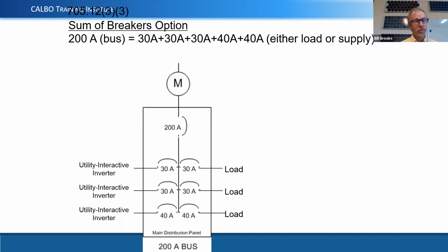And it allows us to put in much more PV, up to, certainly if we're using a 200 amp breaker out of this panel, we could go all the way up to 200 amps, which is 38 kilowatts. That's pretty big on a 200 amp service, more than most people would ever need. Of course, I need it on my house, but that's another story. I'm weird. But even with a 100 amp service, we could do a 100 amp breaker out of our main panel and backfeed 19 kilowatts without having to change out the main service.